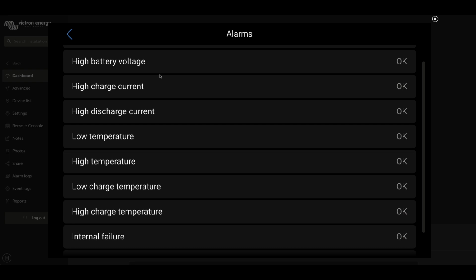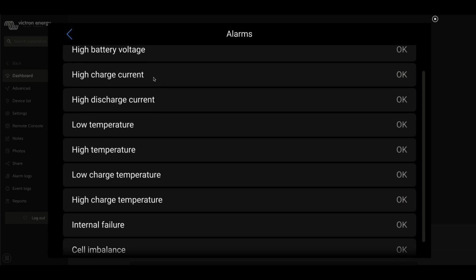And there's a charge current that's running away. High charge current or high discharge current. This would be something that would pop up, more often you'll see this in a small bank or a system that has significant loads. A high discharge current alarm can indicate you have a really big load pulling more than these batteries can provide.